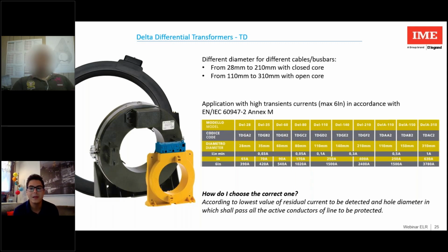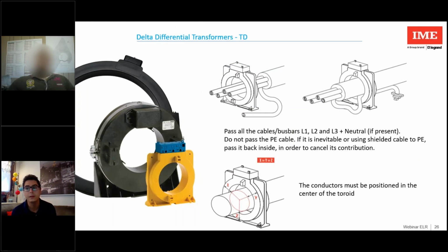So, how do we choose the correct toroid? Well, first of all, I have to know the differential current value at which I want to set the threshold. After, I have to choose a hole, a window, able to embrace all the cable or busbar in an agile way. In fact, I have to pass the cable inside the toroid, trying to center the conductor as much as possible. Be careful not to let the earth conductor pass inside the toroid. If, on the other hand, you have a shielded cable connected to PE, to the earth, pass it back inside in order to cancel its contribution.